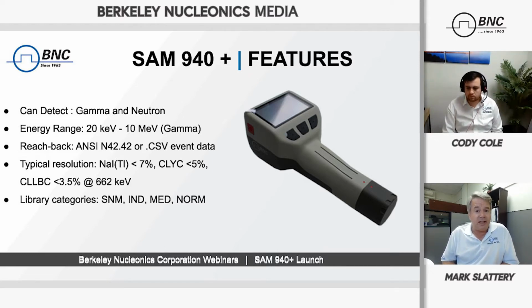The library categories and classifications, of course, we're compliant with the ANSI standards, and so we have a breadth of different classifications in the default library. If you are going to perform your operations in an environment where you're less likely to need to identify medical isotopes or NORM background isotopes, you can switch it to an industrial library, specializing in industrial. Or if you are in a medical environment, change it to medical classifications. If you're out doing a lot of surveying in the field, or particularly if you're looking for enhanced naturally occurring radioactive materials, then you'd probably be using the NORM library as your main focus.